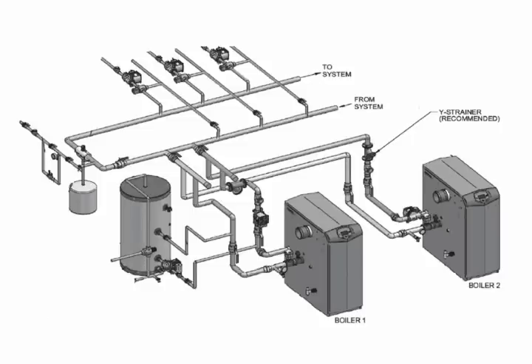So if you look at some of the manufacturers of boilers and their schematics as an example, and some of these are perhaps old, and this is picking an example, I pulled off some of the other extraneous information, but you can see Y-strainers to protect the boiler. You see closely spaced tees, you can see air separation.